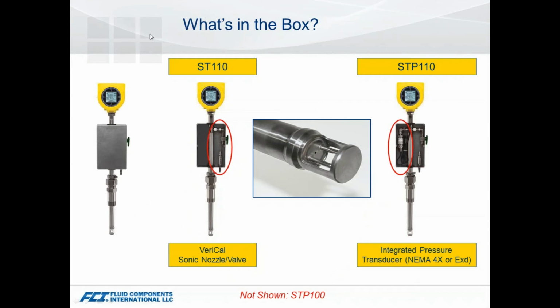When we get into some of our higher end units, we've got a couple of versions that have what we call VeriCal, which is another validation technique, more extensive than an electronics check. Then we have a version we refer to as the STP, where we integrate a pressure transducer. We have a port in the flow element and a tube that accesses the process pressure that goes up through that flow element. Depending upon features, whether it's just VeriCal, pressure, or both, we tap into that tube. If you look at the center here, you can see how small that opening is that gives us access to the process condition.